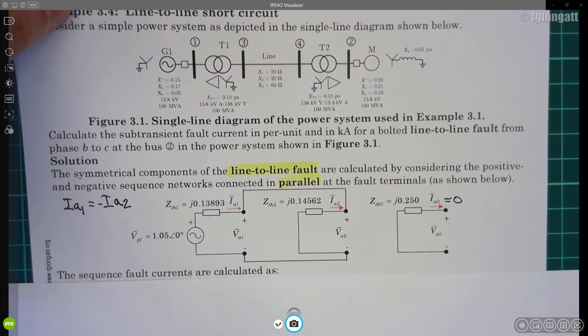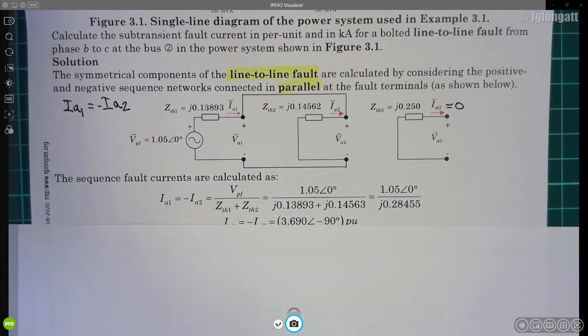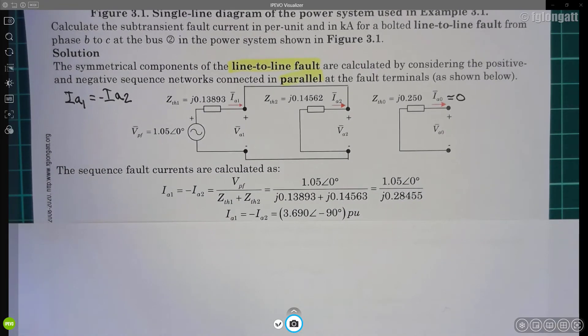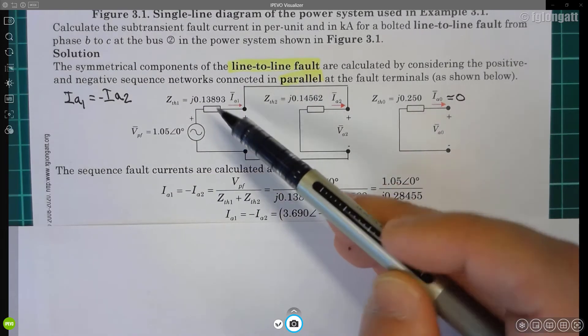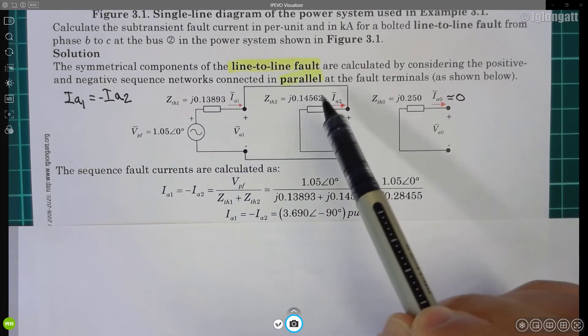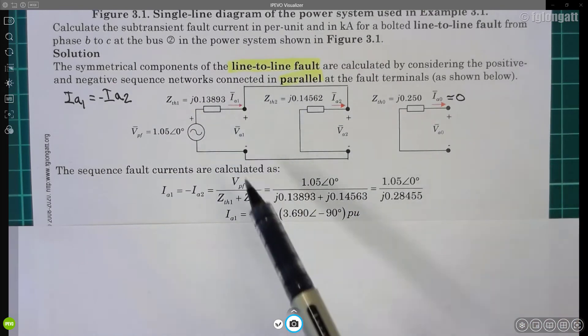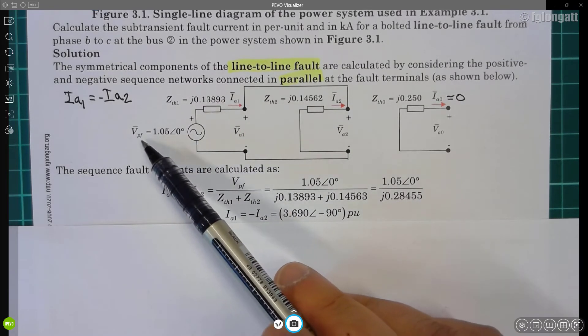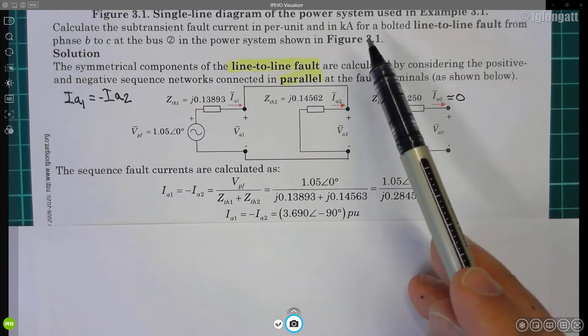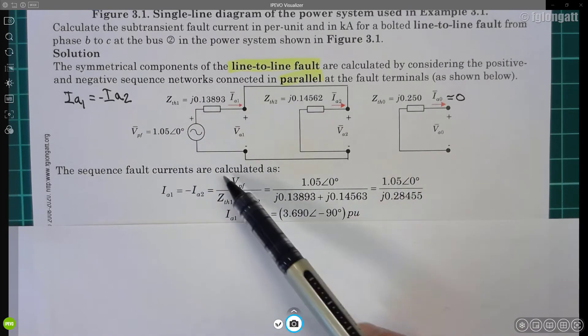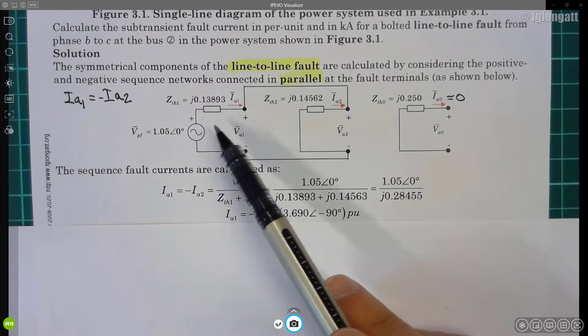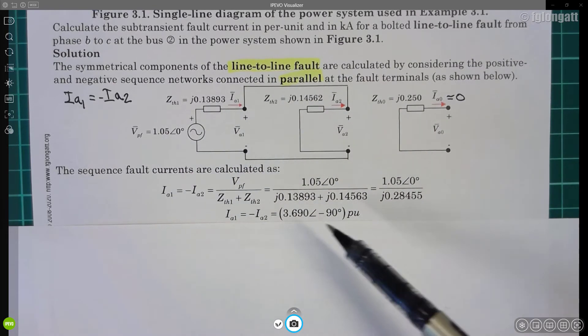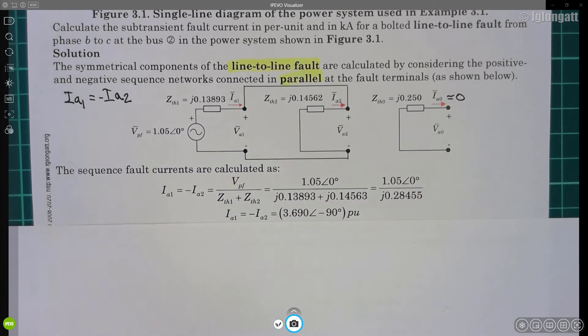The next step is to define the interconnection of the sequence networks — they are connected in parallel — and my students can use various circuit analysis techniques to calculate the positive and negative sequence currents. For instance, the positive sequence current equals the voltage divided by the total impedance. There is only a single voltage source inside the positive sequence model, coming from the pre-fault voltage. We found in example 3.1 that voltage is 1.05 per unit. Dividing by the series combination of positive and negative sequence impedances, we obtain the per-unit current.